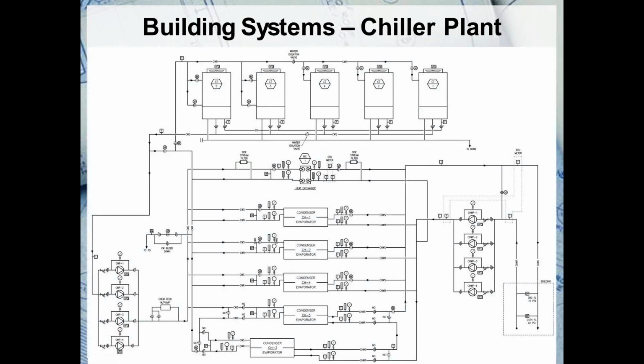So let's jump into some of the building systems. The chiller plant in this building is located in the penthouse. The plant consists of 5 York centrifugal chillers, 3 of which are 800 tons and 2 of which are 400 tons. If you look on this flow diagram, chillers 3 and 5 are piped in a series counterflow configuration, which means that the chilled water enters chiller 3 before going on to chiller 5, and the condenser water enters chiller 5 before flowing into chiller 3. So there's a counterflow configuration there. These series counterflow chillers are then headered in parallel with the remaining 3 chillers.